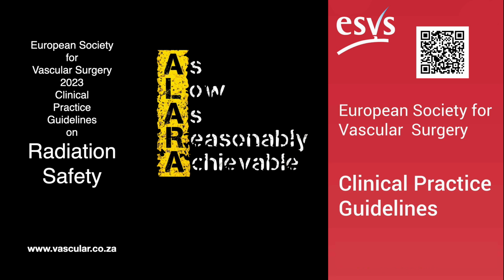Okay, that was a lot on techniques. Let's quickly summarize the key practical takeaways for dose reduction. Good idea. So ALARA is the goal. Think about pedal time, short taps, last image hold. And be incredibly mindful of DSA: lowest frame rate necessary, limit runs, consider fluoro loops instead. DSA is a huge dose driver. Collimation is your friend. Use it aggressively to reduce scatter. Think about removing the grid for low scatter cases.